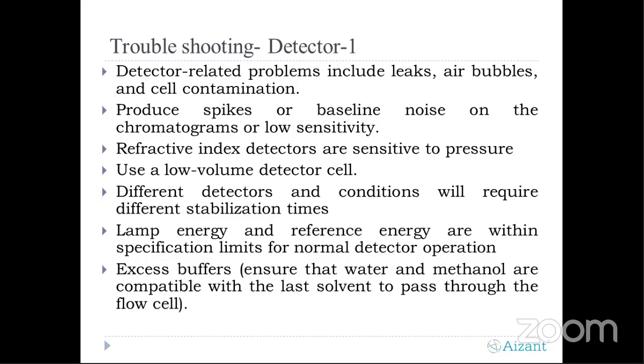So the first problems which come from the detector: you'll find a leak in the tubing connected to the detector, or an air bubble entrapped in the detector, or cell contamination. Leaks mean a connection problem. How do air bubbles come to the detector? I discussed this in the first slide on the mobile phase. If the degassing of the mobile phase is not done properly, these minor air bubbles will slowly go through the tubings, and the detector is the only part after the pump where they can accumulate. Initially you will never face any challenges in the baseline, but the next day your runs are lost. You will find a very zigzag baseline appearing. You can't even identify your peak of interest. It's because of the entrapped air bubbles.